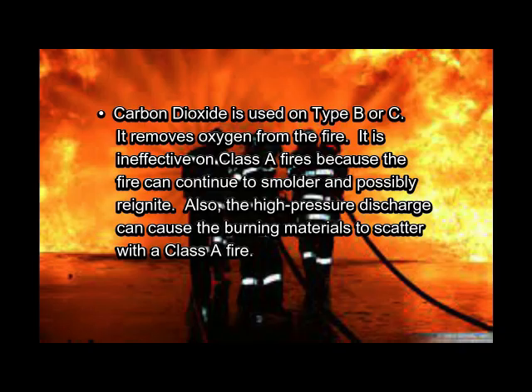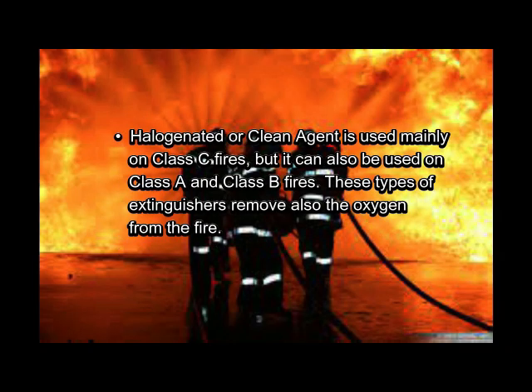Carbon dioxide is used on type B or C. It removes oxygen from the fire. It is ineffective on Class A fires because the fire can continue to smolder and possibly reignite. Also, the high-pressure discharge can cause the burning materials to scatter with a Class A fire. Halogenated or clean agent is used mainly on Class C fires, but it can also be used on Class A and Class B fires. These types of extinguishers also remove the oxygen from the fire.